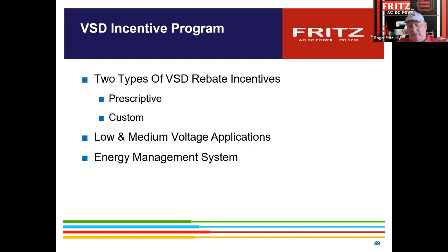There's low voltage, up to 480, 575 volt. They consider the 200 to 575 volt all low voltage rated. We also do medium voltage controls that go from 2300 volt up to clear up to 13K if you need, because they do build inverters that actually build power. They transmit power DC and then put inverters on the back end side. But the majority of stuff we deal with is medium voltage, which is 4160 volt motors in America. Sometimes there's 6,000 volt overseas.